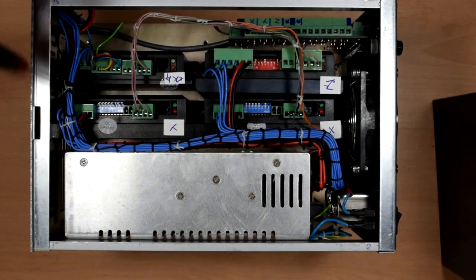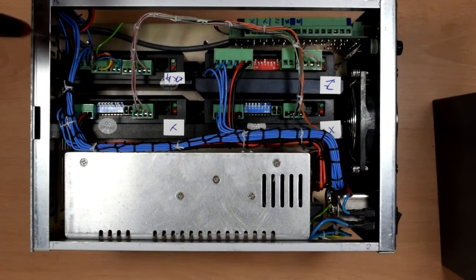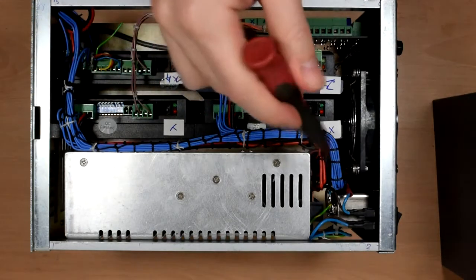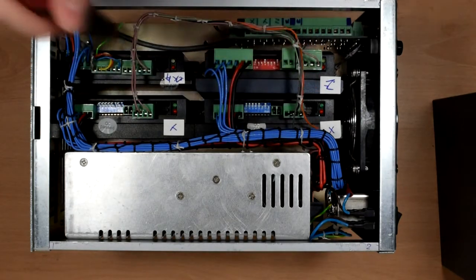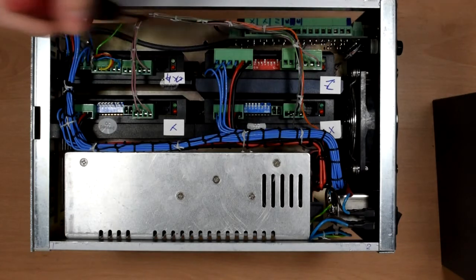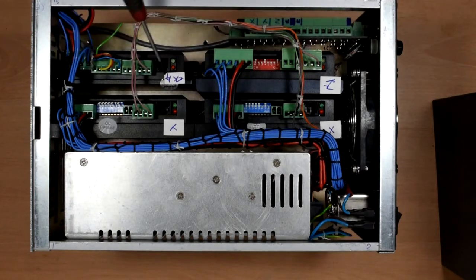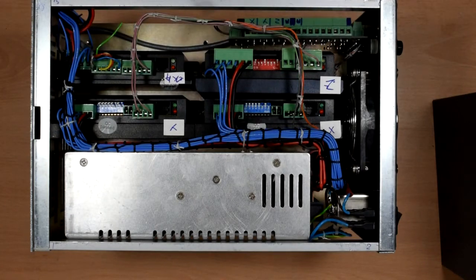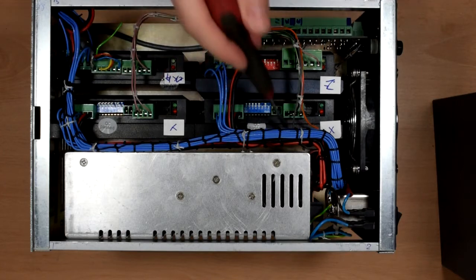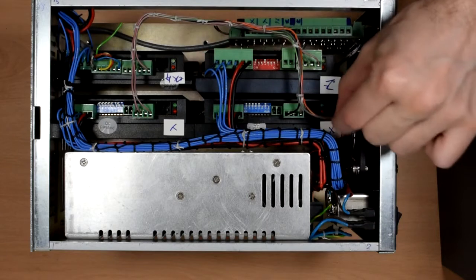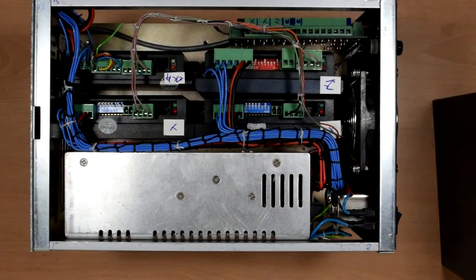This kind of construction where you have all the noisy signals coming in from one direction and all your signals going from the other direction is absolutely critical. If anyone out there is doing something like this, do not cross any of these over. These are actually just power lines and even this routing here is sub-optimal but there is no other way to do it.